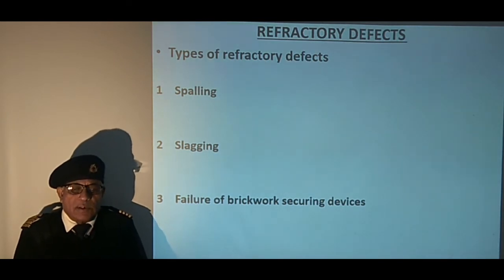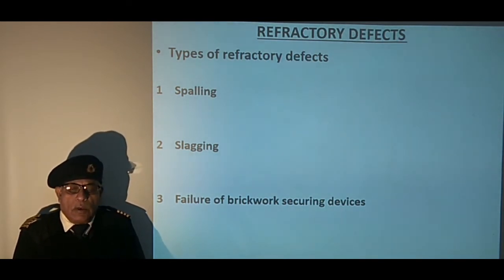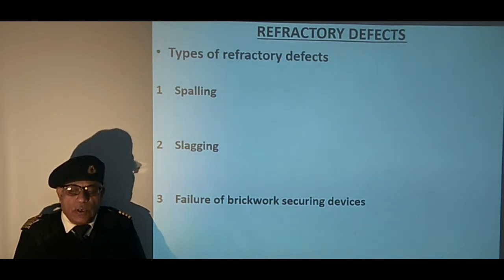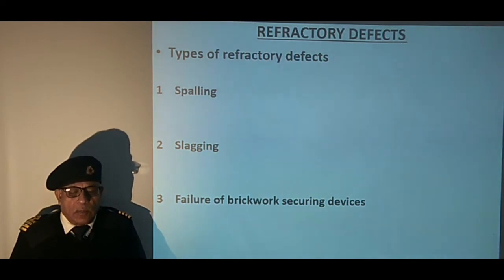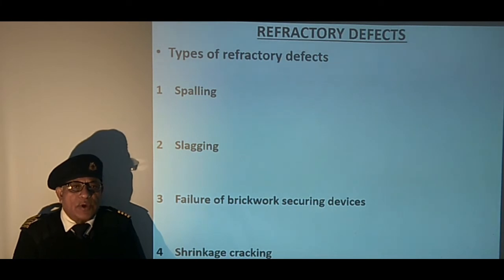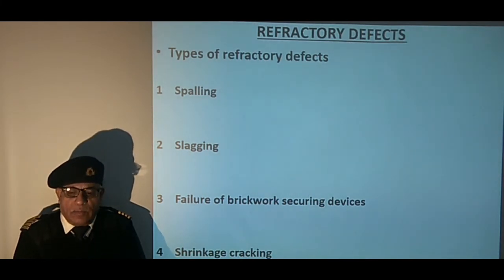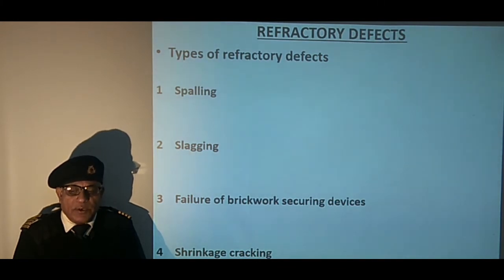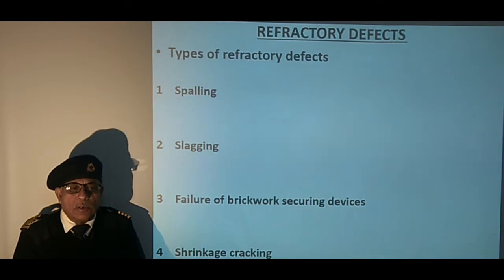Bricks which are secured by bolts may have a tendency to crack in case the bolts get exposed and fail due to overheating. Refractory materials are weaker in tension than in compression or shear. Sudden compression after the expansion of brick at high temperature may result in cracking if cooled suddenly.